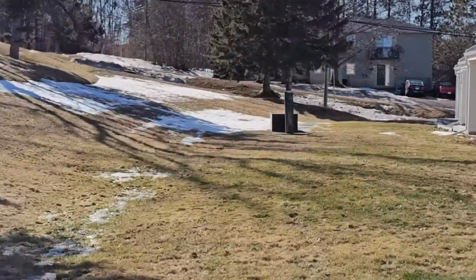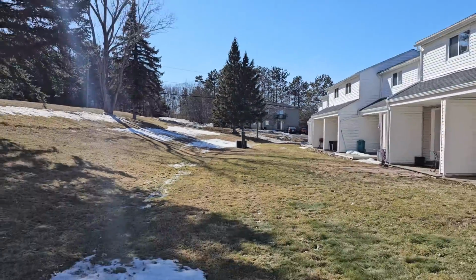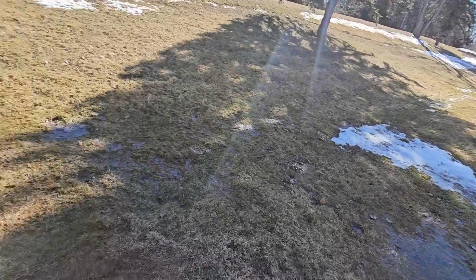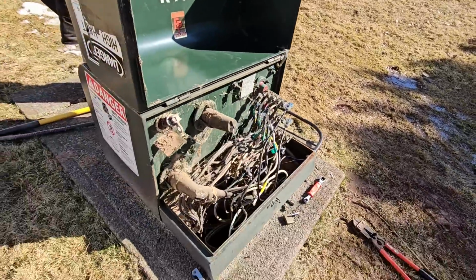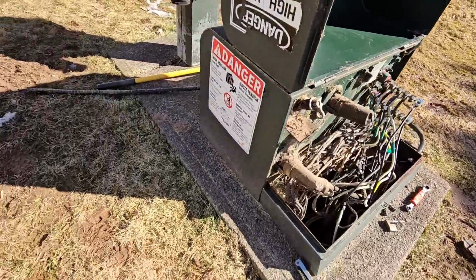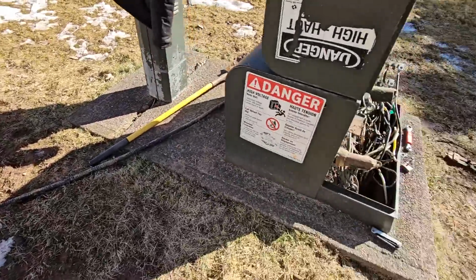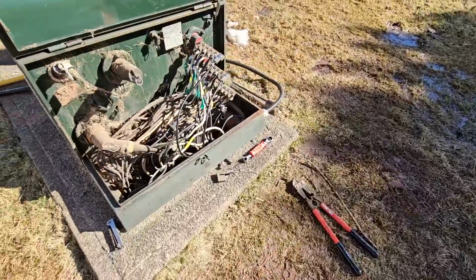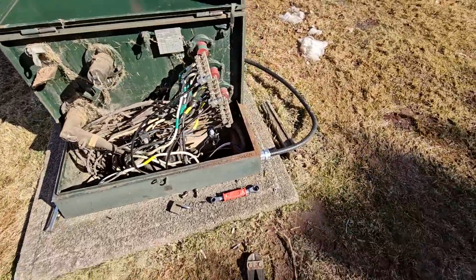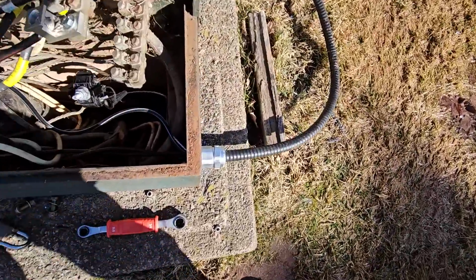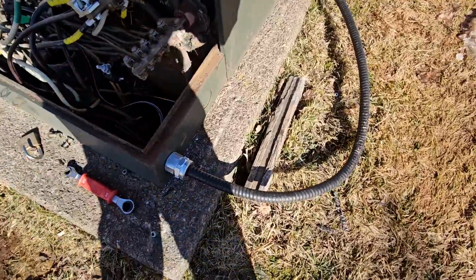So with this temporary feed, now that the customer has power, we can take our time and do a more proper fix. We're going to change the pad mount and install a secondary box to run the conduits into, which we'll take a look at in a moment. We did have to get some special permissions from the engineering group as well as the provincial inspectors in order to do this.